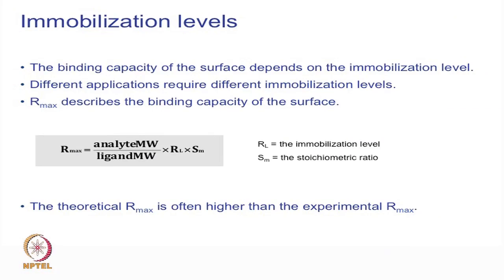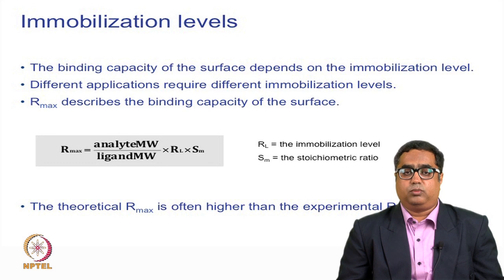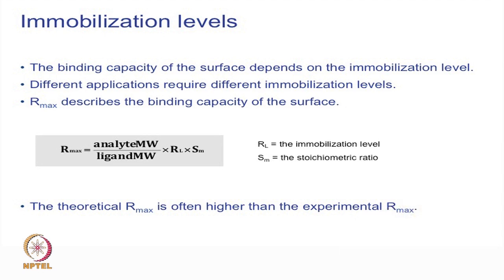Most proteins are generally immobilized at 10 mM sodium acetate buffer pH 4.5, but this is a general assumption. Immobilization level can be set by two ways: either a controlled immobilization process aimed at a calculated R_max based on stoichiometry, binding level, and number of binding sites, or by a time-and-flow mode where you flow the molecule at a particular pH for a set time and flow rate, and whatever immobilization happens at the end is the immobilization level.